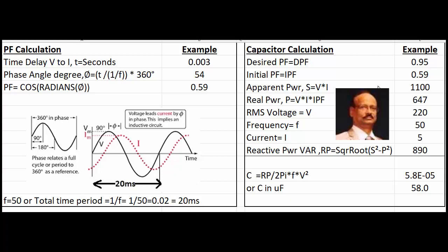For the capacitor calculation we have taken the same figure. The desired power factor is say 0.95 and initial power factor is 0.59. Apparent power is equal to V into I which is equal to this, and then the real power is this where the power factor is also multiplied. In the RMS voltage we have taken 220, frequency 50 hertz, and the current is about 5 ampere. The reactive power VAR is this much. The capacitor value by this formula is 5.8 times 10 to the power minus 5 or 58 microfarad. So this is the basic understanding of the theory.